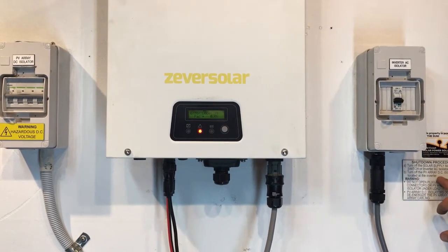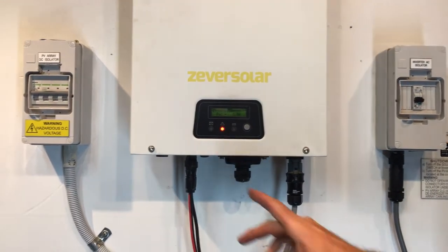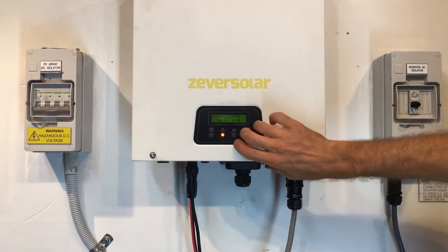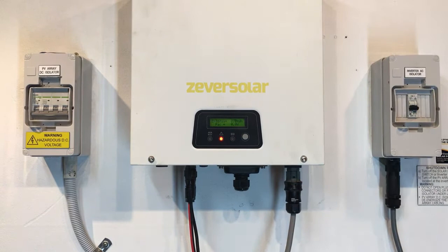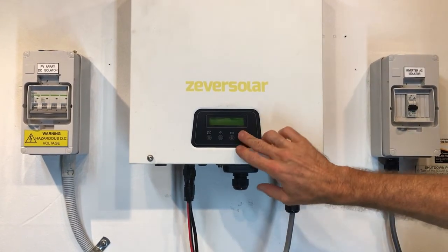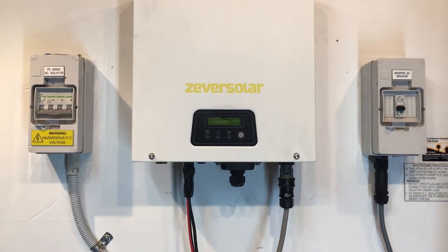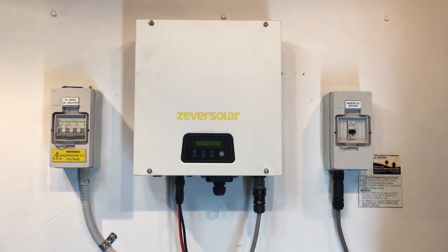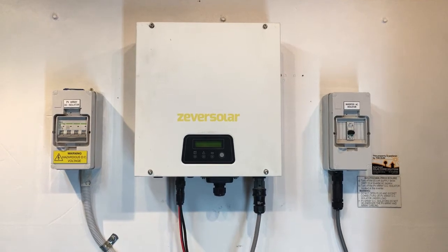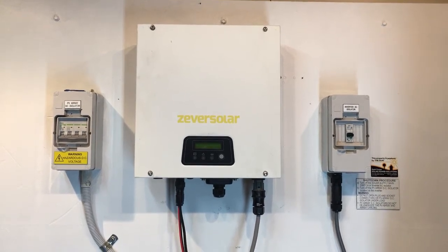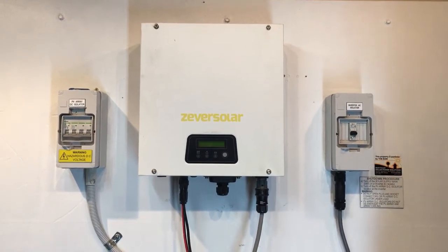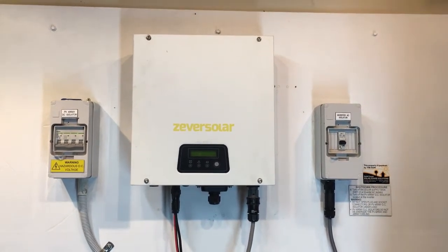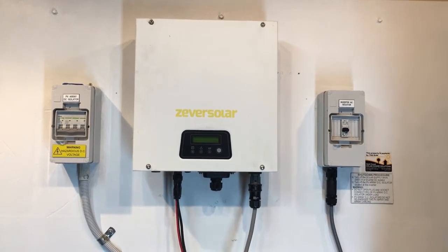And then we have to turn off the PV array DC isolator located at the inverter, which is over this side. And you should see the inverter, after a few seconds, go completely blank, just like so. Then the manual recommends that you leave the inverter off for 3 minutes, and then you attempt a reboot of the system and see if it clears the error code 3 message. So we're just going to fast forward now 3 minutes.